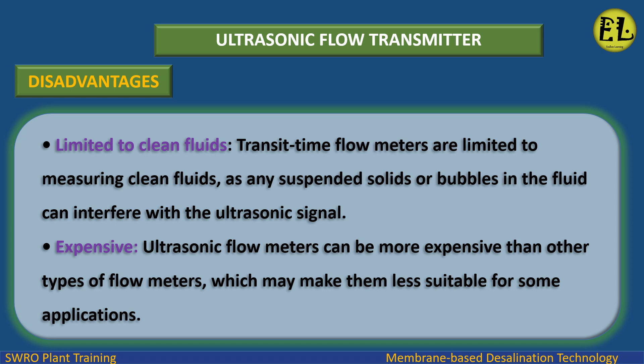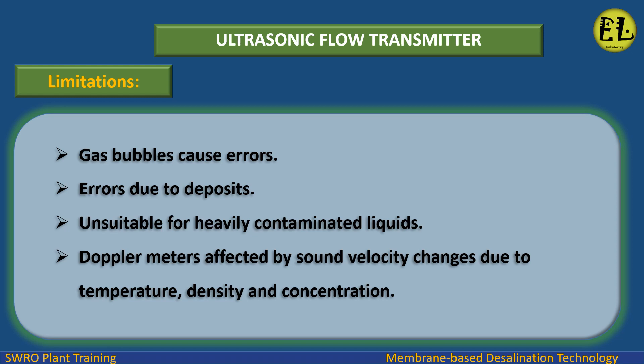Disadvantages: Transit time flow meters are limited to measuring clean fluids, as any suspended solids or bubbles can interfere with the ultrasonic signal. Ultrasonic flow meters can also be more expensive than other types of flow meters. Limitations include: gas bubbles causing errors, errors due to deposits, unsuitability for heavily contaminated liquids, and Doppler meters being affected by sound velocity changes due to temperature, density, and concentration.